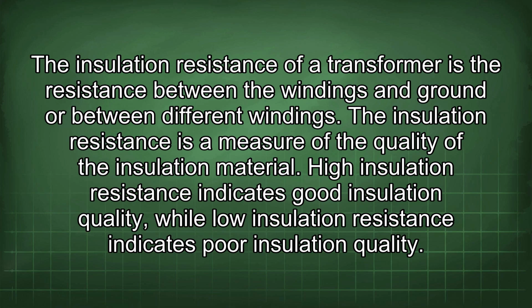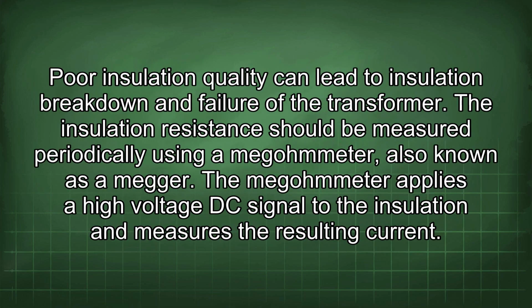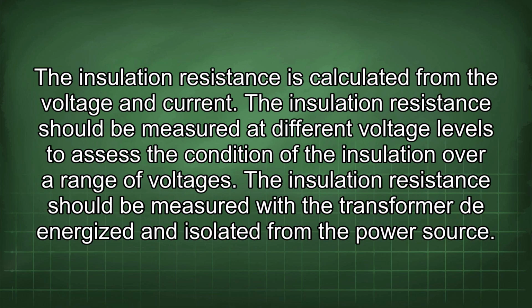The insulation resistance is a measure of the quality of the insulation material. High insulation resistance indicates good insulation quality, while low insulation resistance indicates poor insulation quality. Poor insulation quality can lead to insulation breakdown and failure of the transformer. The insulation resistance should be measured periodically using a megohmmeter, also known as a megger. The megohmmeter applies a high-voltage DC signal to the insulation and measures the resulting current. The insulation resistance is calculated from the voltage and current.